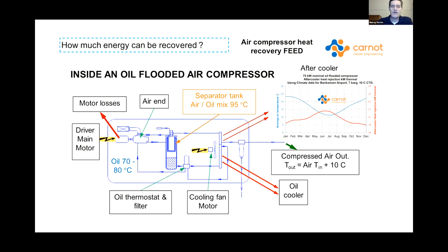As far as where all the heat comes and goes, about 85 to 90% of the energy is provided to your main drive motor. Of that, 5% is lost due to motor efficiency losses. If you've got a VSD, that'll add another 2 to 5% in the electrical losses going to the drive motor. And you've got your cooling fan motor as well, that will use between 2 to 5% of the compressor's nameplate power. So you'll reject 70 to 80% of the heat to your oil cooler and 20 to 30% to your after cooler.